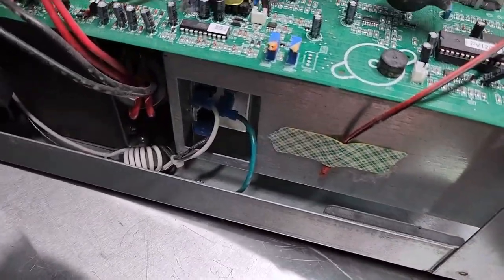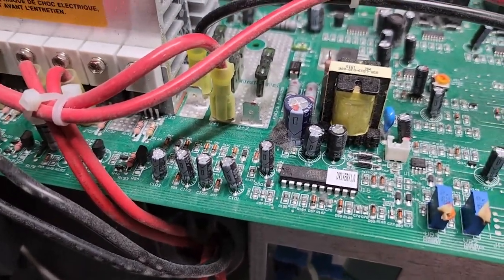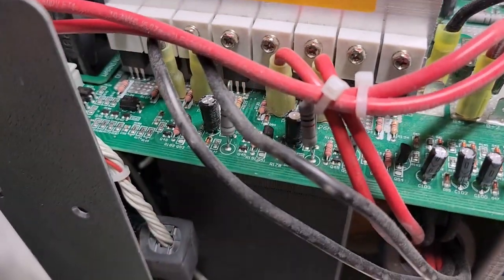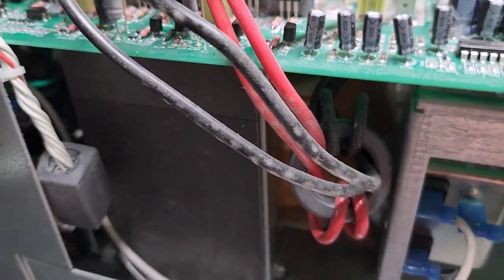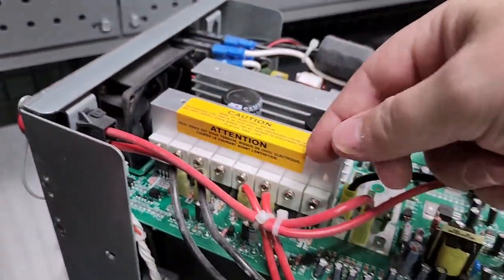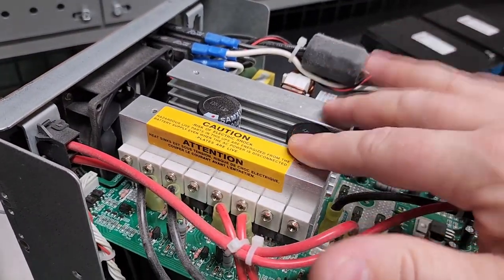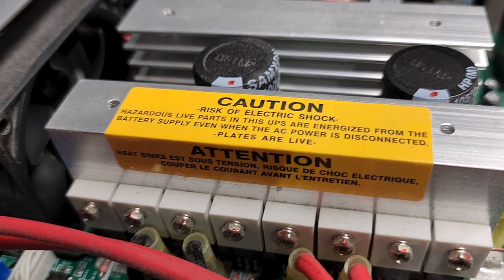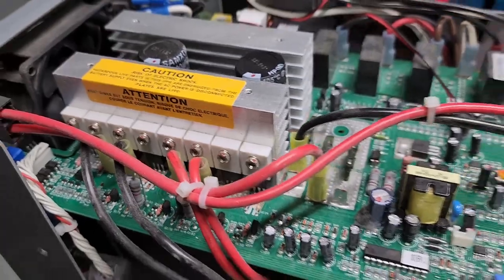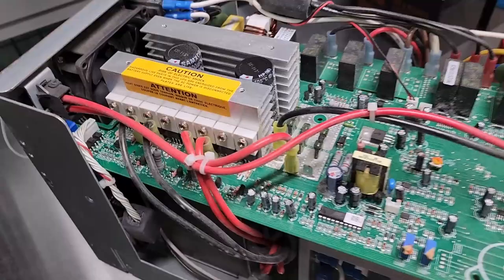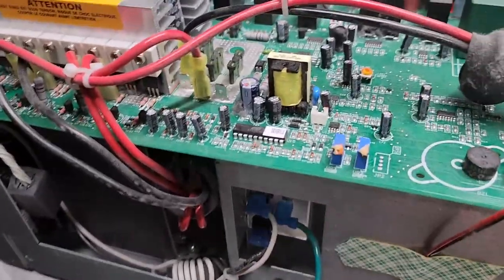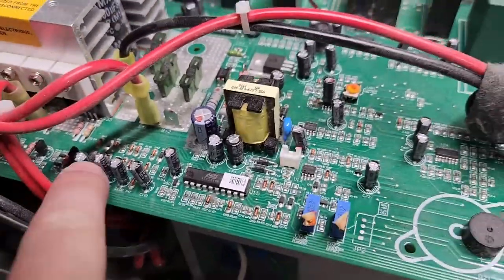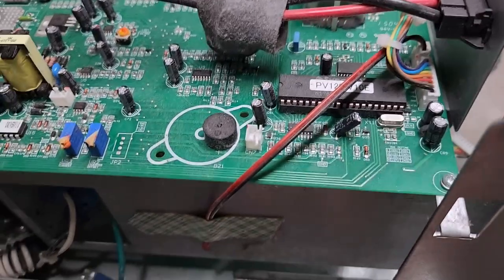Some of the things that I look for on these UPS systems is all these electrolytic capacitors. You want to make sure that they're not leaking, and you can see right here, I've got a fuzz that's up in here. So, this board has got to get blown out. It's going to get cleaned up. All these terminal connections right here, they're all going to be checked. Mind you, it's not plugged in because these heat sinks can be live. They can be hot.